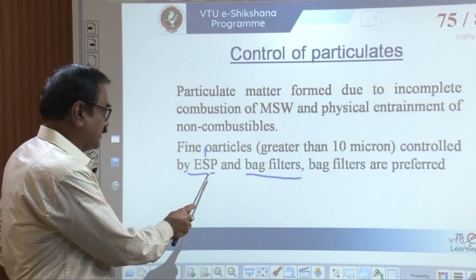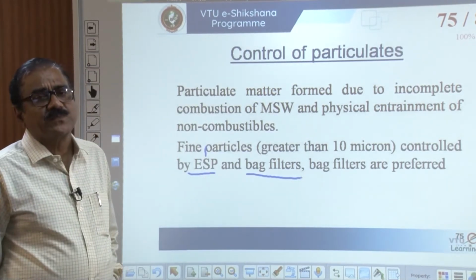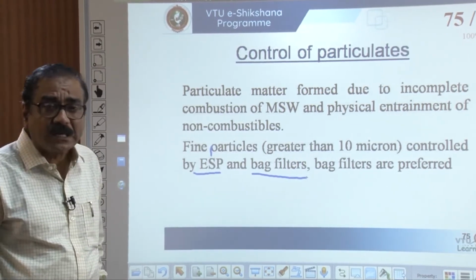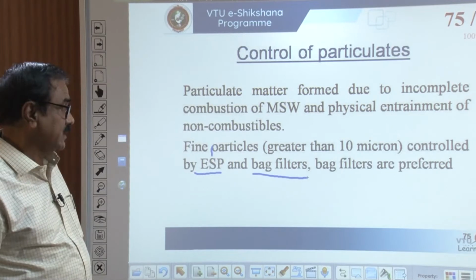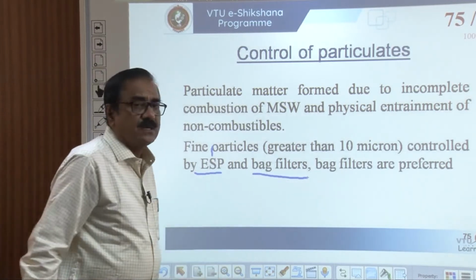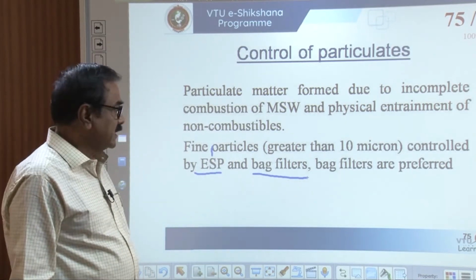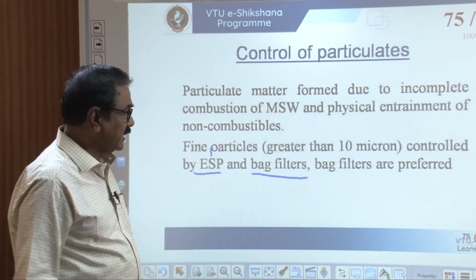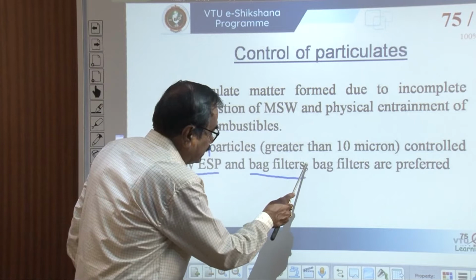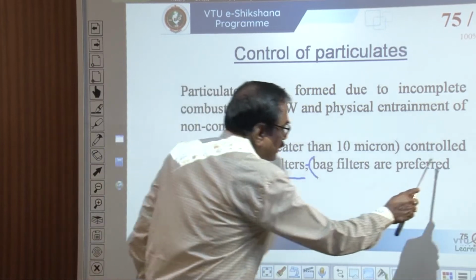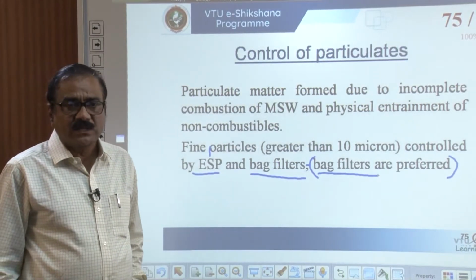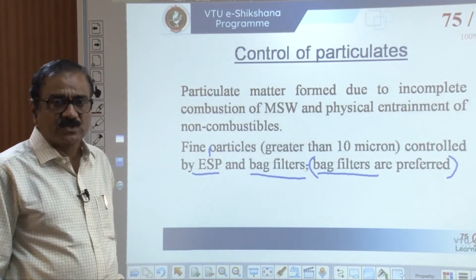Practically, electrostatic precipitator is a very costly process, and as far as particulate matter generated during municipal solid waste management is concerned, I think bag filters are more than sufficient. They are not only economical but also very efficient. Actually, bag filters are preferred to control the particulate matter generated during the combustion of the commingled municipal solid waste.